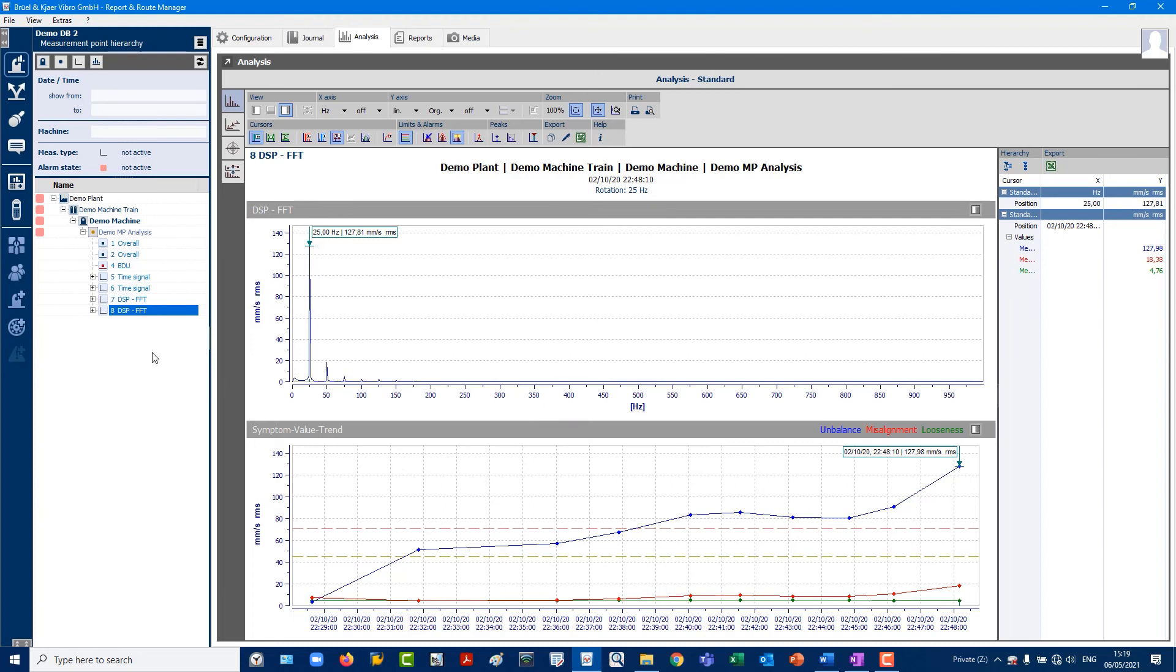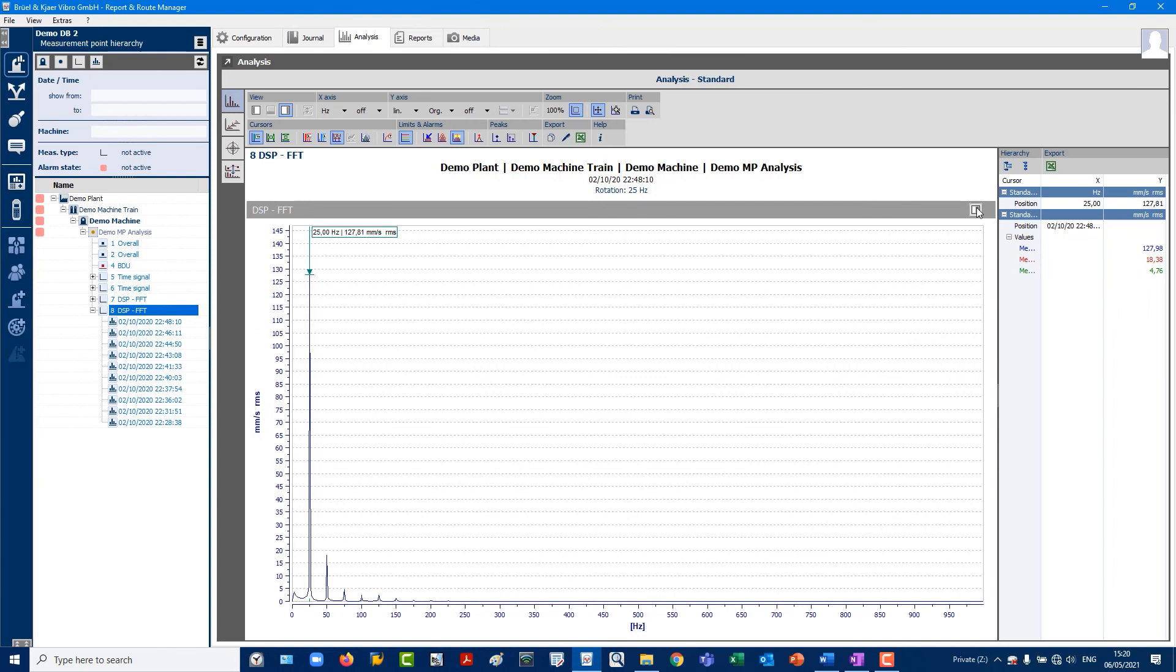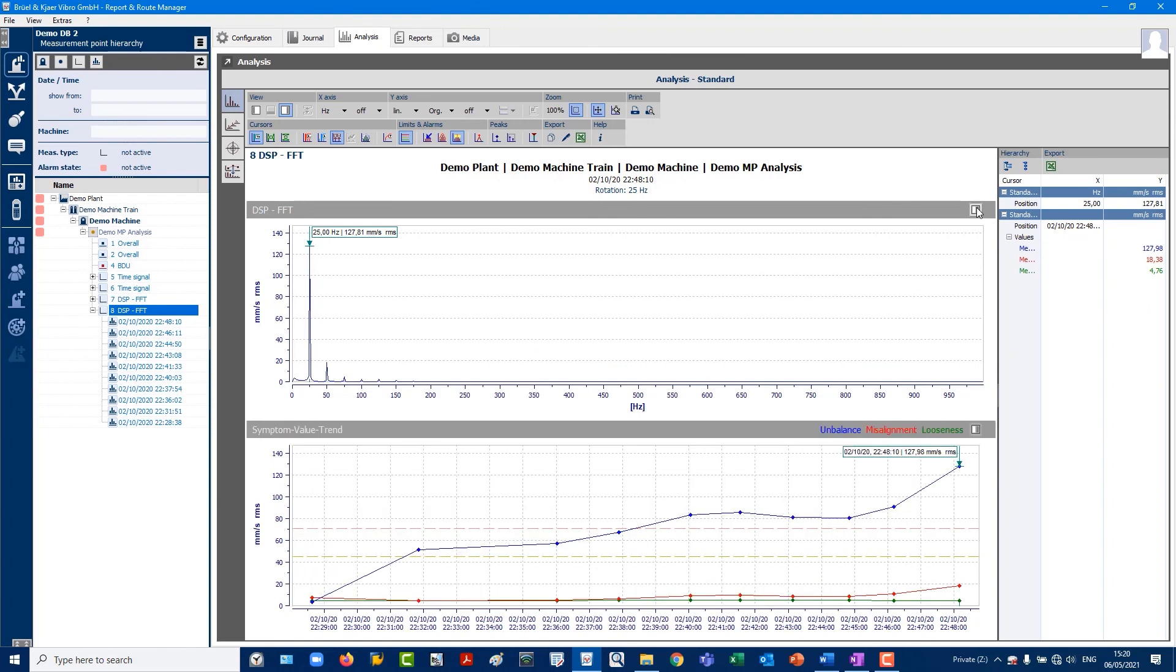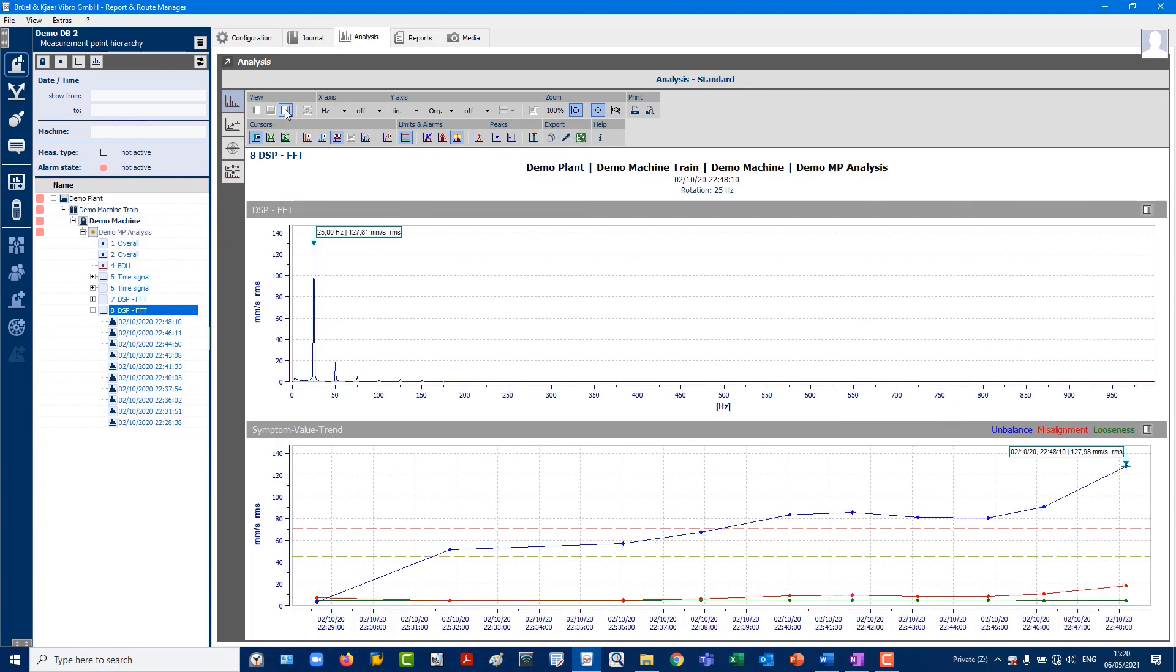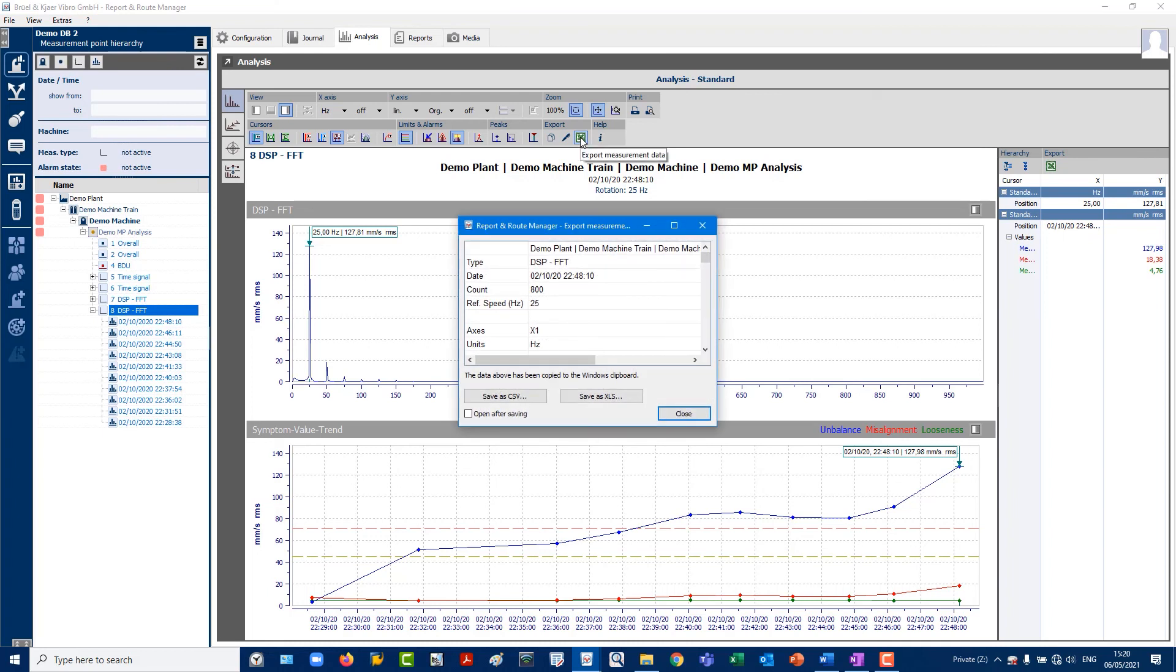Please note, these are only indications. The dependency for a definite fault diagnosis on 1x, 2x, 3x is more complicated and requires further measurements to confirm diagnosis. Typical analysis characteristics could be view the FFT by clicking on the icon in the upper right corner, display cursor values in the cursor readout area, export the measurements to Excel. All other functions can be found in the user manual.